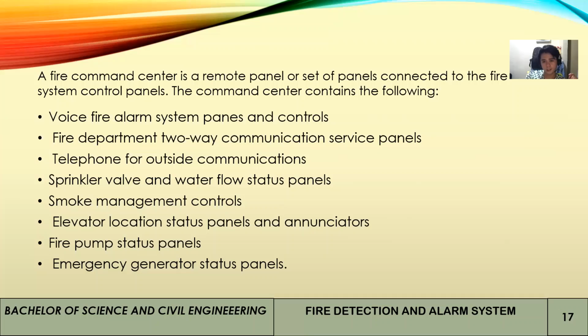The command center contains the following: voice fire alarm system panels and controls, fire department two-way communication service panels, telephone for outside communications, sprinkler valve and water flow status panels, smoke management controls, elevator location status panels, annunciators, fire pump status panels, and the emergency generator status panels.